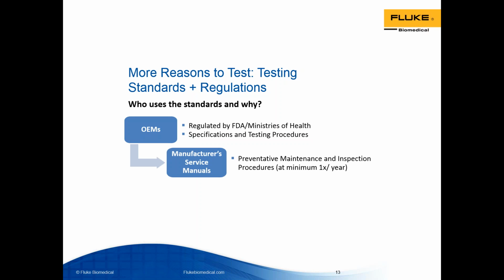As we all know, a manufacturer's service manual will contain procedures specific to the maintenance and performance of the device, and they'll typically recommend an inspection frequency too. While these testing workflows tend not to be quite as thorough as the standards, each manufacturer will apply the standard to the best testing for the design of their brand and model of infant incubator. So the manufacturer's service manual will give model-specific directions to test the incubator, such as the need to ensure that warning lights turn on when they should. So if the temperature is too high, the alarm should sound, sort of thing.